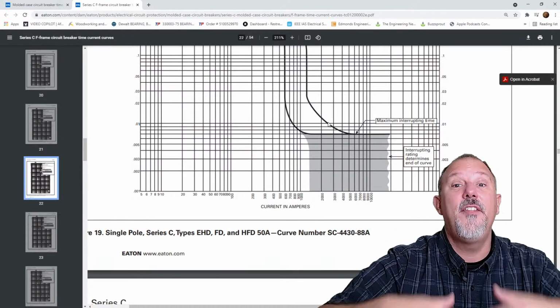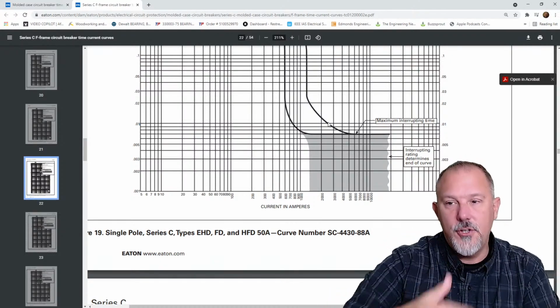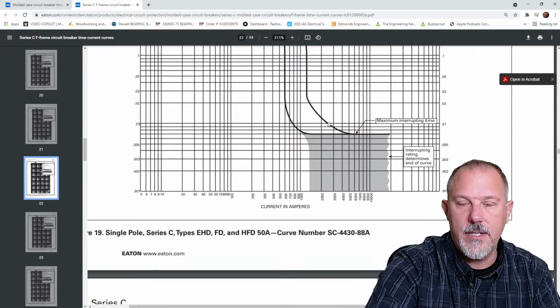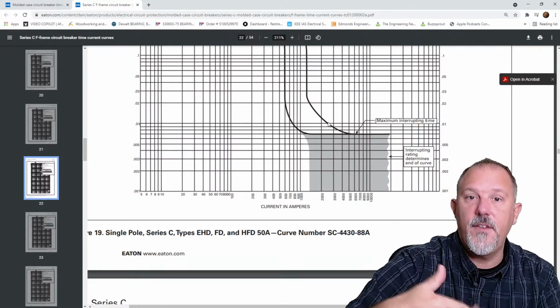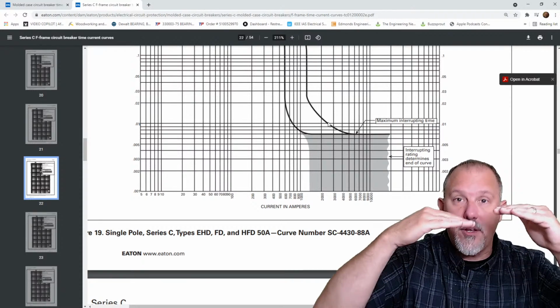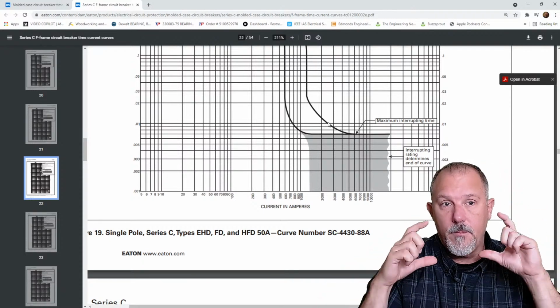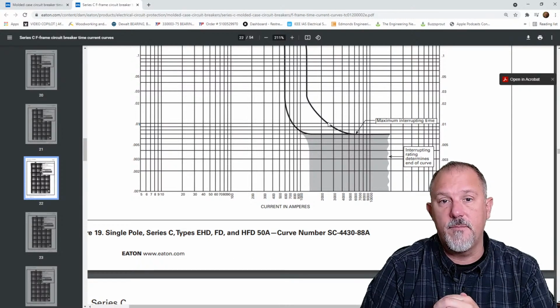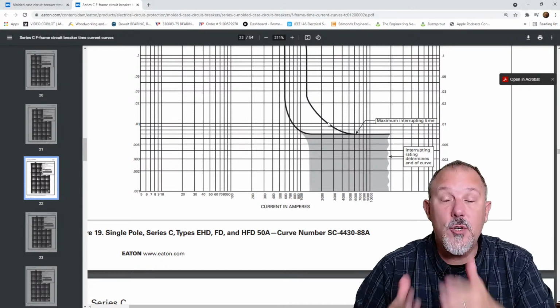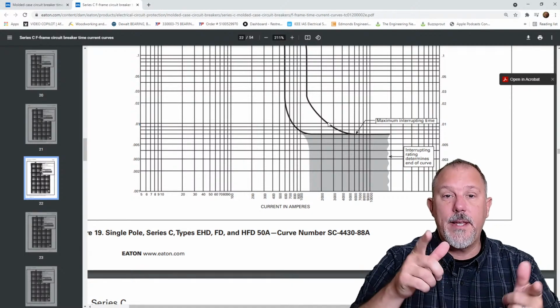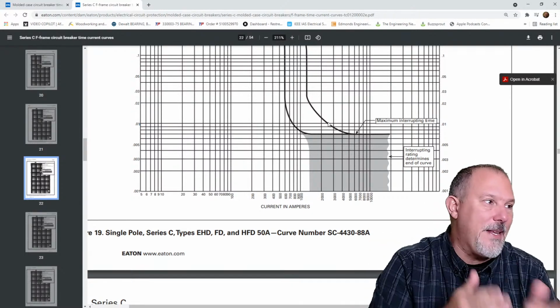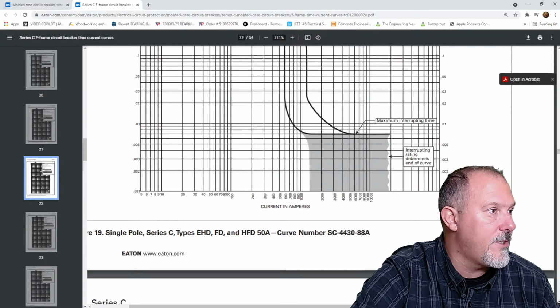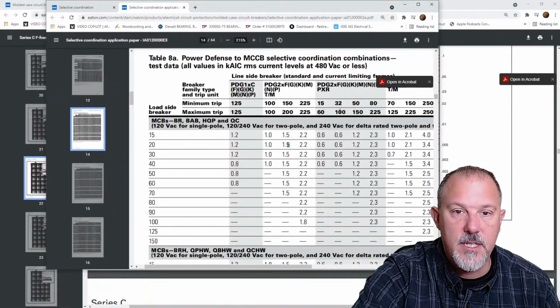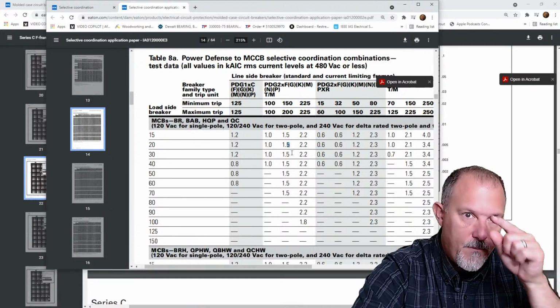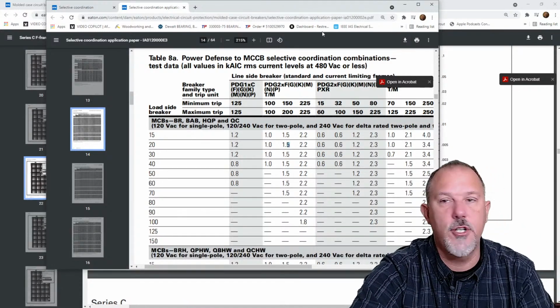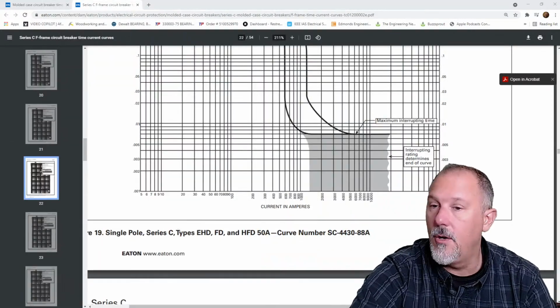But in reality, there is data that could be shown on a selectively coordinated system on the TCC curves if it's put into SKM and you increase the margins within what's plotted on a TCC curve. But rarely do we do that. Whenever we get to fault currents that are high enough, we rely on these tables. That is what we do. We pick these tables. These tables will tell you what will happen to those two breakers beyond a certain current value. I can tell you they'll both open or they won't.